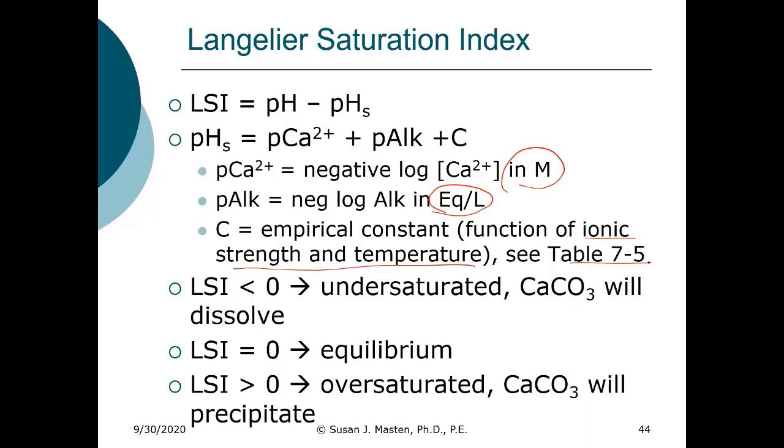Now, if the LSI is less than 0, that means that the water is undersaturated with respect to calcium carbonate, and you would expect that calcium carbonate would dissolve. So that would mean that the calcium carbonate that is precipitated in the pipes, that provides a coating on the inside of the pipes, prevents the contact of the water with the free metal.